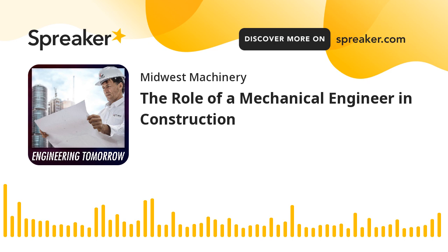So sometimes it's just a check of, are we still working towards that end goal. In construction, then it's about how that design intent is being delivered. We like to have earlier involvement to see early on whether things are being installed the way they need to be, both per design and per manufacturer's installation instructions, because manufacturer A may have slightly different requirements than manufacturer B. And when the design drawings go out, the engineers don't know that, so there's potentially a correction to be made in the process. We try to get involved as early as possible to minimize the impact to the contractors on the team, as well as ultimately the owner.